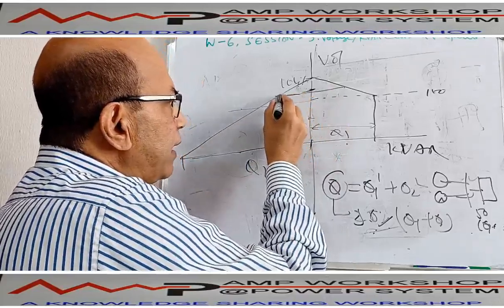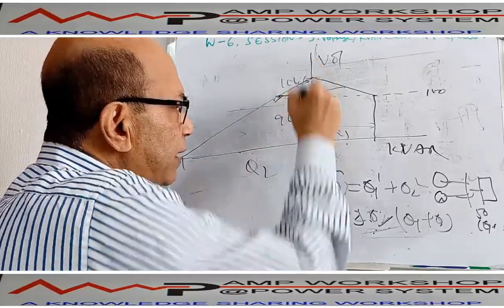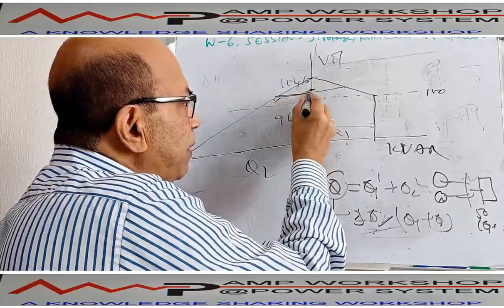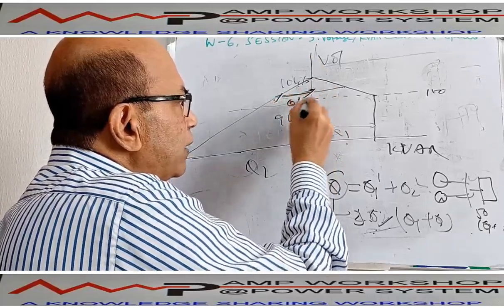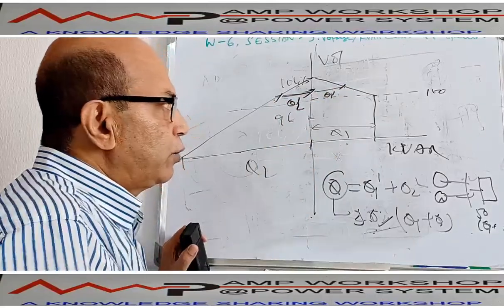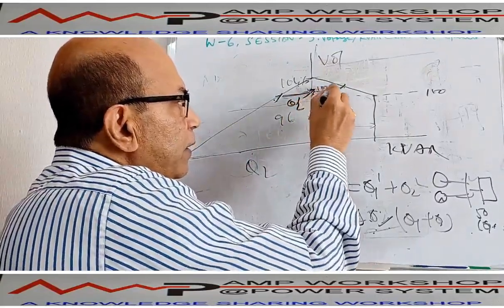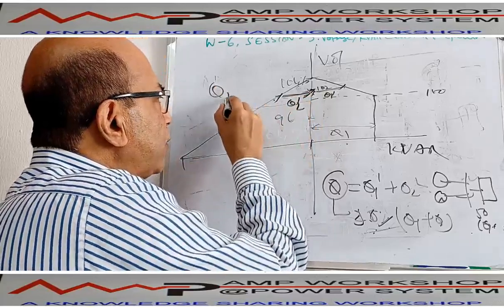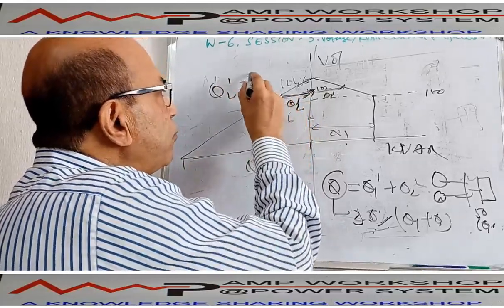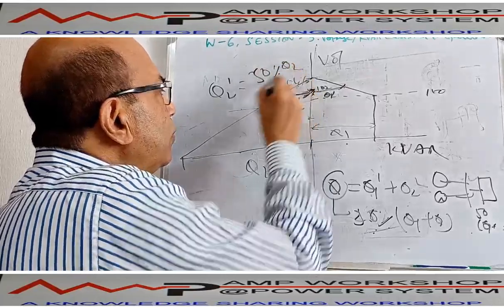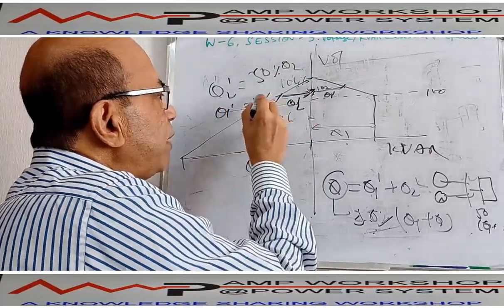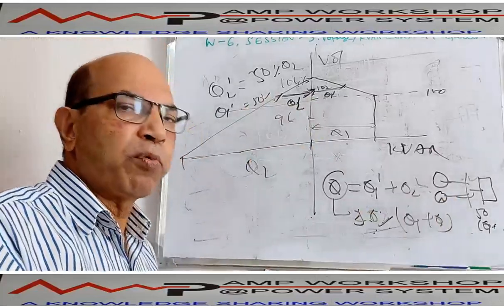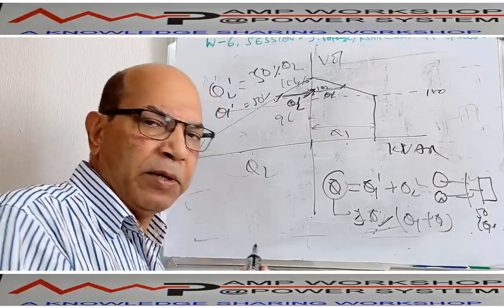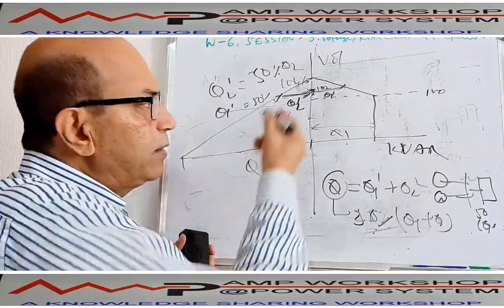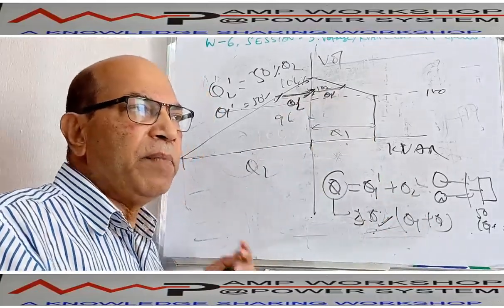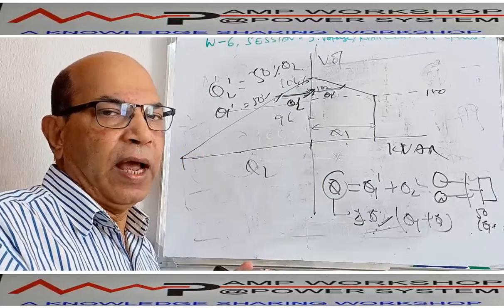This should actually be 50%. I have not drawn it, this scale is not right. So this is actually 50%. This will be Q2 dash, and this will be Q1 dash. At 100%, Q2 dash equals 50% of Q2, and Q1 dash will be 50% of Q1. So both the machines will be loaded in proportion to their capability.